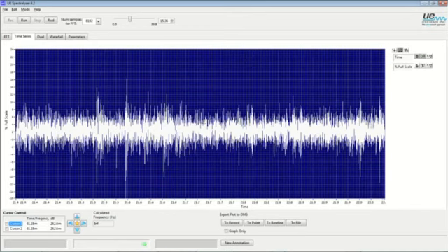And now we get an even closer view, looking at our broadband white noise here, and I'm going to focus in particular on these several peaks right in here. And what I'm interested in is, will the timing between these big discharges be similar? It's a little hard to tell right here, but you can see there's differences. On this very first one, we can see there's several discharges tied together, and then we have one large one here with a couple smaller ones. So I'm going to zoom in on these two or three right here and take the time base down even further.